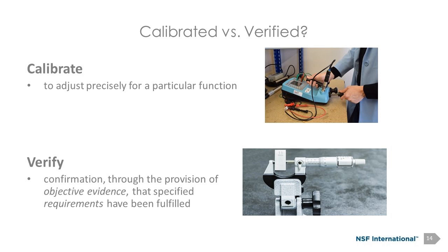Calibration versus verification. Now, by the definition, calibration is different than what we've known calibration to be for all of our careers. We've always used calibration as this encompassing bucket to include all verification, monitoring, measuring equipment, the metrology, whatever we want to call it. In reality, calibration is a verb that talks to adjusting precision or adjusting precisely for a particular function. So we calibrate, we adjust the tool to meet the requirement. Versus verification is confirming through the provision of objective evidence that specified requirements have been fulfilled.